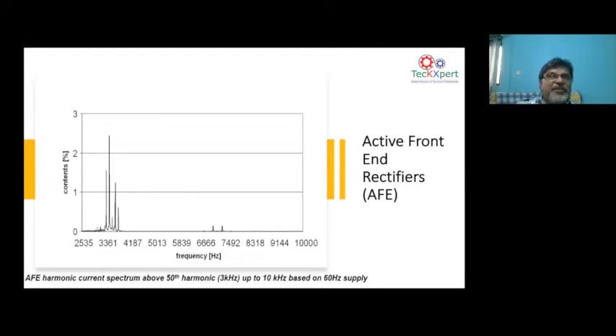So that means 3,600 harmonic frequency currents will flow in the network. You have higher frequency harmonic currents generated by the active front end. You can see here, near the 50th harmonic, that is at 3 kilohertz, between 3 kilohertz and 10 kilohertz. This 3.3 kilohertz is the high frequency current generated by the active front-end drive. That means whenever you go for this low harmonic drive, it also produces higher order harmonics. So that is again dangerous to the network. As I told you in the beginning, it can sometimes cause transient over voltages.